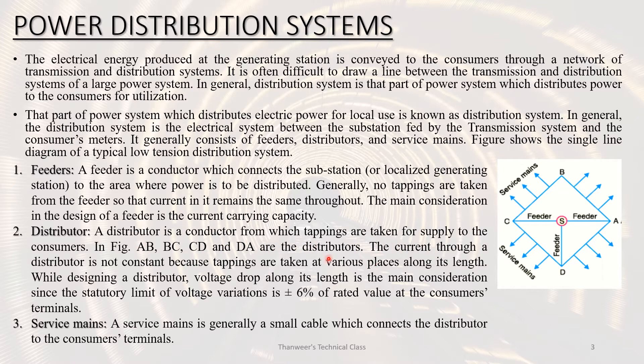A distributor is a conductor from which the tappings are taken for supply to consumers. The distribution side voltage should be maintained within plus or minus 6 percent of the rated value at the consumers' terminals. A service main is a small cable which connects the distributor to the consumer's premises.